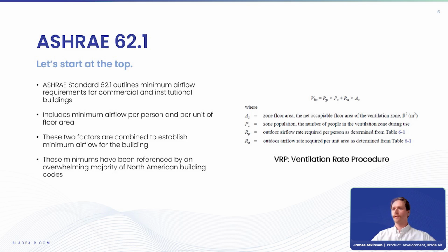So there's two factors. There's first a per person and then a per unit of floor area, right? So the per person ventilation requirement is to account for things like breathing, so bioeffluents, infectious bioaerosols, so if people are sick and coughing, all that sort of thing. And then the per unit area, that's to account for building generation. So if you have building materials that are off-gassing, right, new furniture, that formaldehyde smell, different pollutants from building operations. So if you're in an auto shop, you're using lots of harsh chemicals, things like that. So it's very easy to implement, right? You just have to look up at a table, what kind of building you're using, what kind of activities you have. You can choose those variables, you plug in your population, your space, you're done. You know how much air you need to deliver.